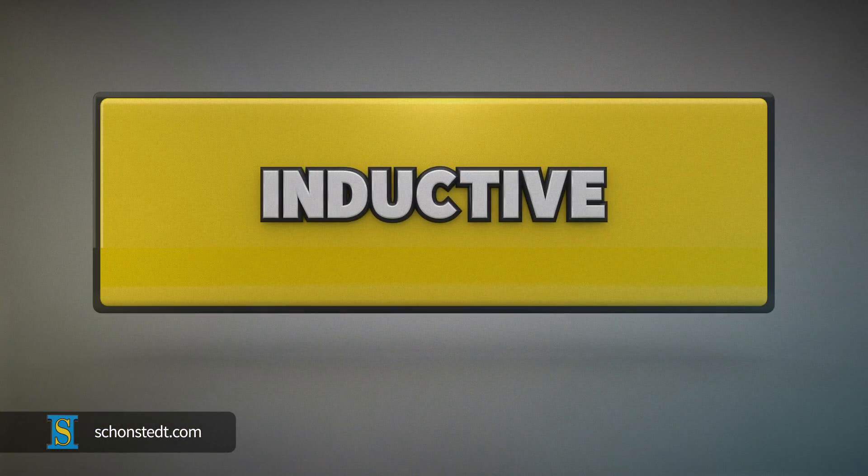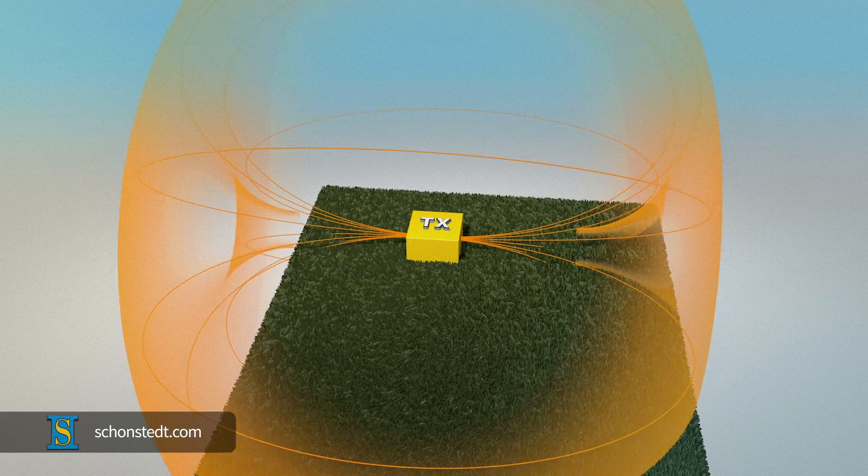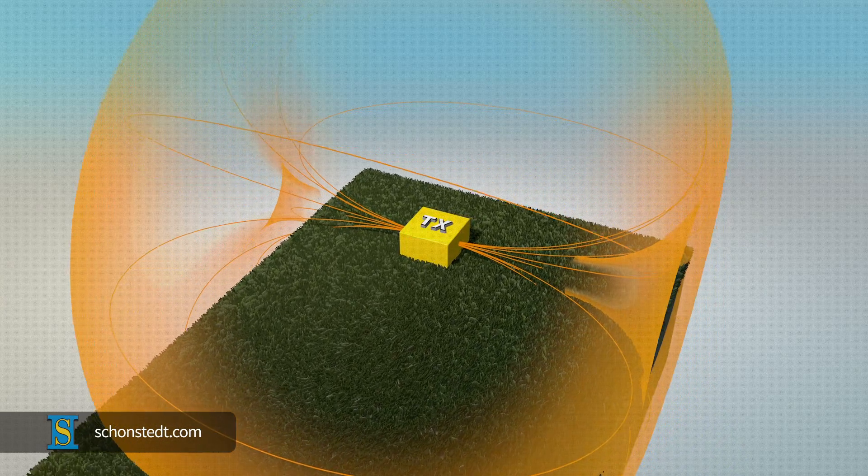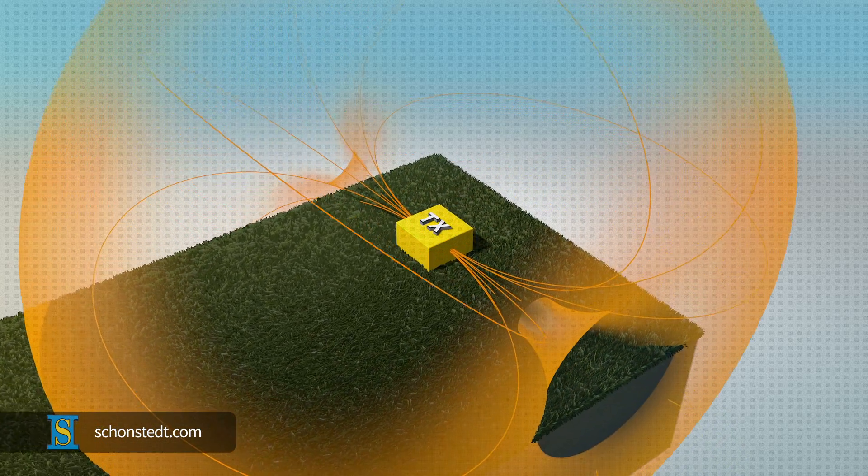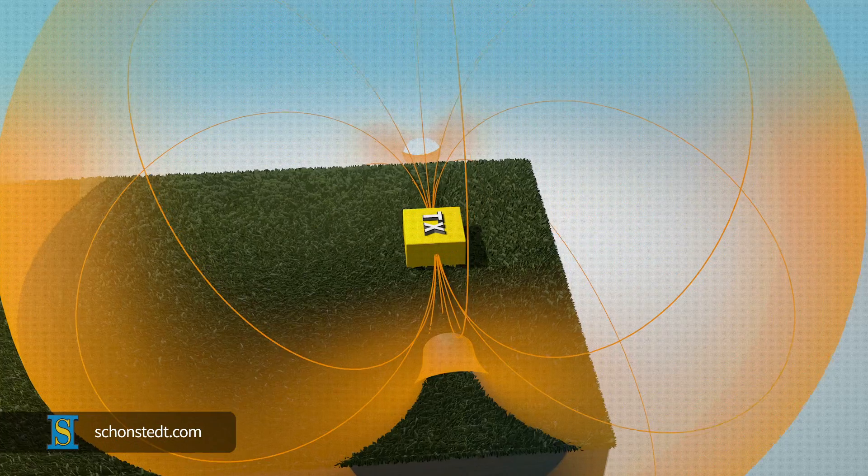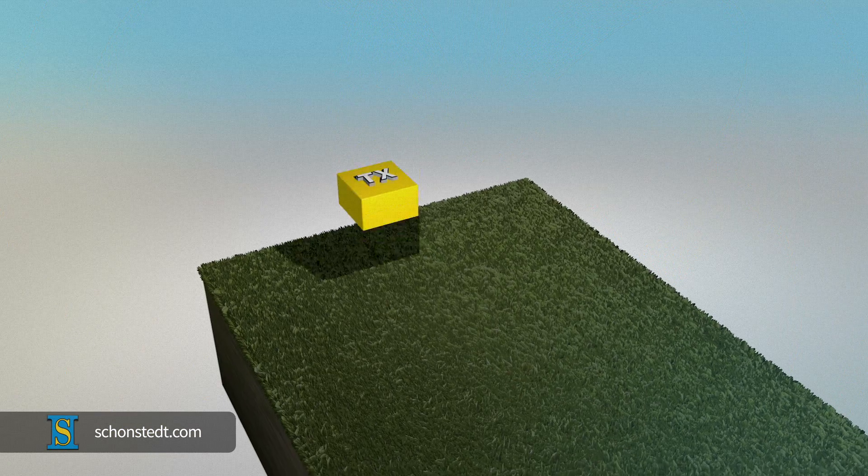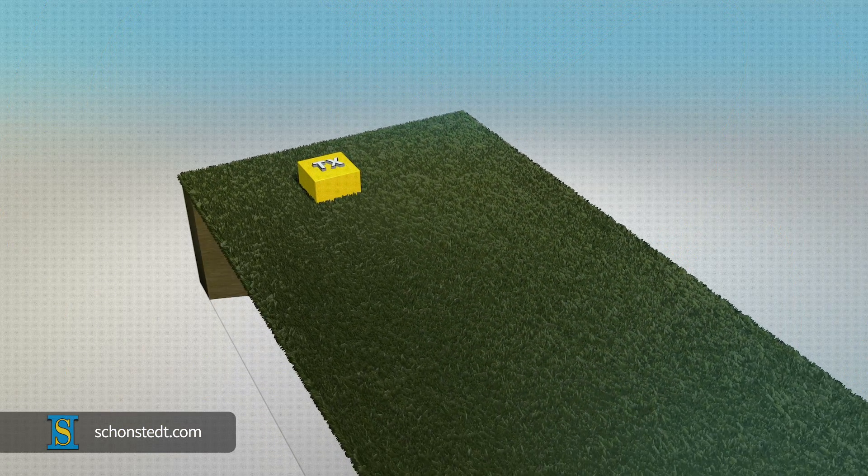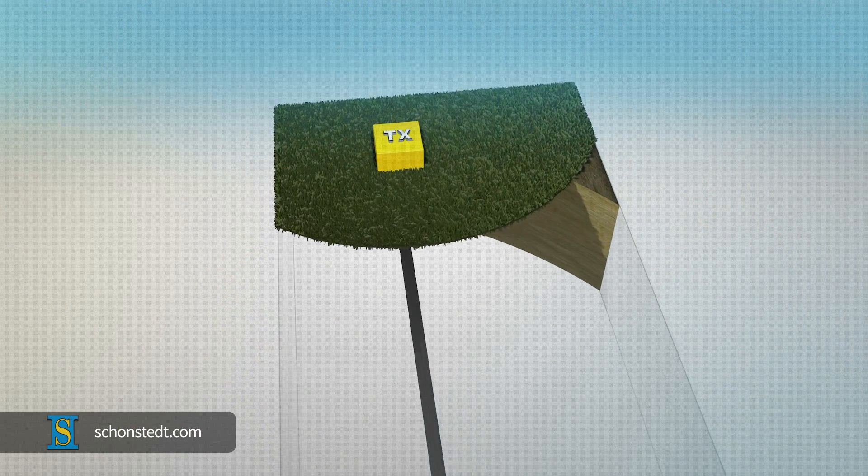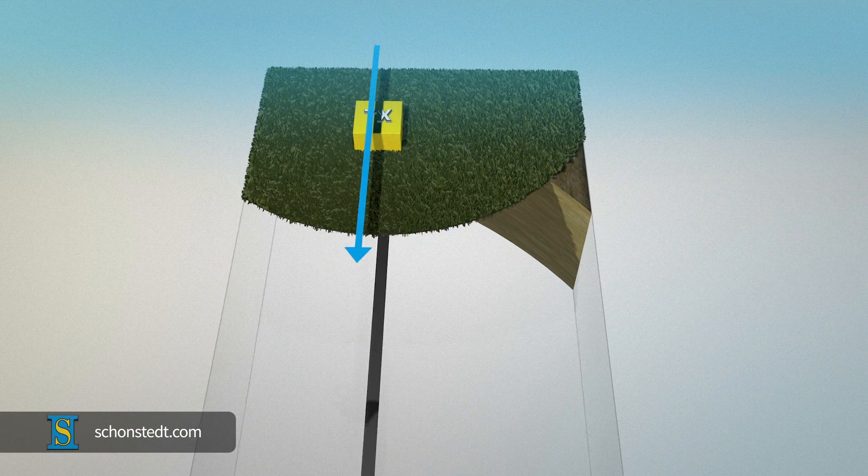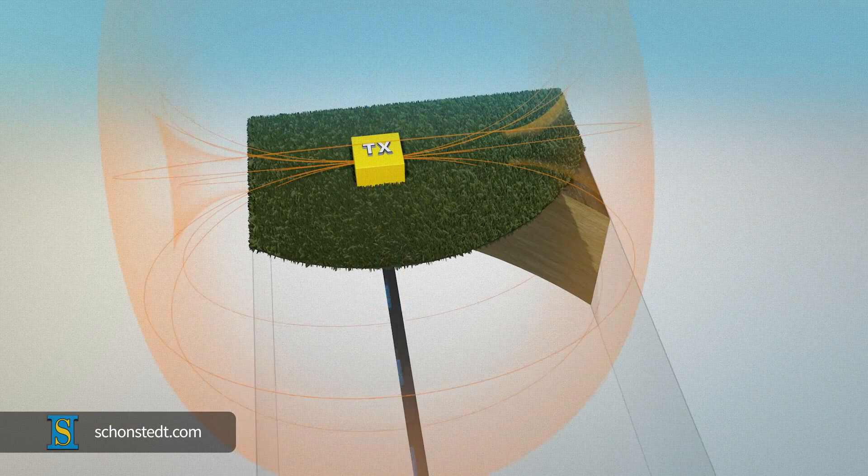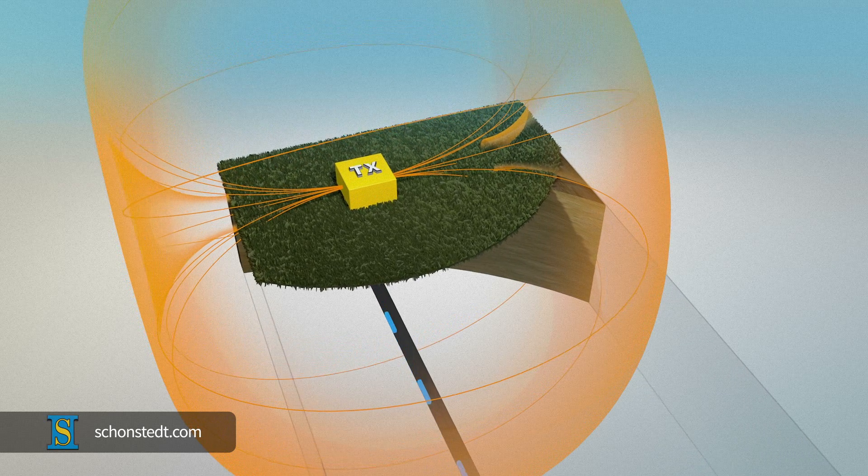For the inductive method, an antenna that is either built into the transmitter or attached to it as an accessory generates a signal that induces a current on the target pipe or cable. Place the transmitter, or the antenna attached to the transmitter, on the ground, directly over the pipe or cable. The arrow on the label should be parallel to the anticipated trace line direction.